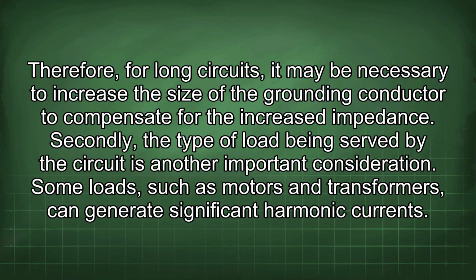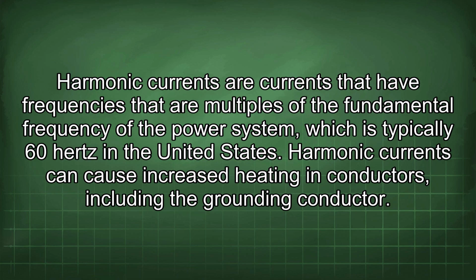Some loads, such as motors and transformers, can generate significant harmonic currents. Harmonic currents are currents that have frequencies that are multiples of the fundamental frequency of the power system, which is typically 60 Hz in the United States. Harmonic currents can cause increased heating in conductors, including the grounding conductor.